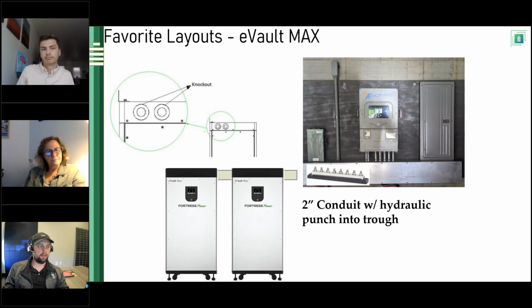To summarize, if you need to increase your capacity with the Evault Max batteries, you just parallel them together. It's a 51.2 volt battery, and most of your systems are essentially going to be nominal 48 volt, so you're going to parallel them together—you never would series them. We don't ever recommend seriesing any lithium battery for that matter. Using bus bars to essentially parallel them is the best practice.